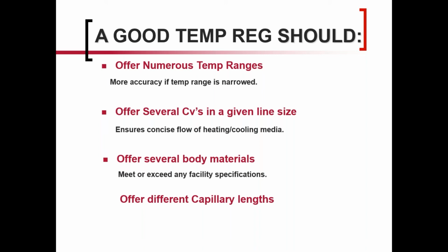Several body materials, this is pretty straightforward, just so that you meet or exceed any facility specifications. And that comes up a lot with refining, a little bit in pulp and paper, the type of thing where you've got plant specs that you need to meet. So, more materials than just say like a cast iron should be available. And then offer different capillary lengths. So a lot of times where you want to measure the temperature in a tank is not real close to where the steam line is. So, if you have variable capillary lengths, that makes the actual installation easier. But again, if the point of reading temperature is, let's say, 30 feet away from where the actual steam source is, if you've got capillary lengths that go that far, then you don't have to repipe any steam lines. So again, installation is made a little bit easier through that means.